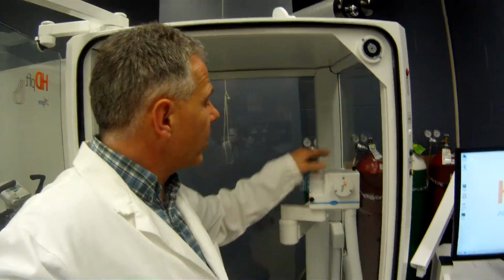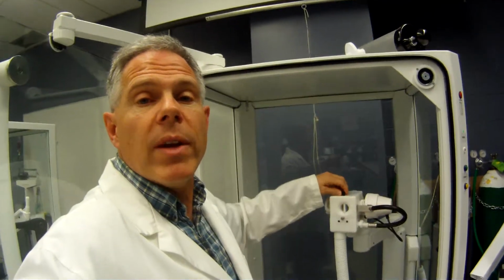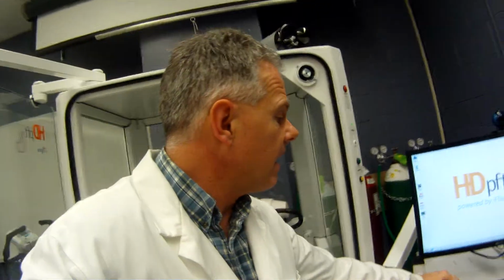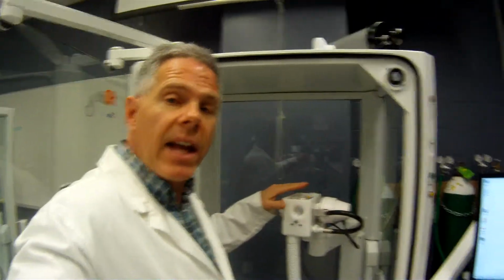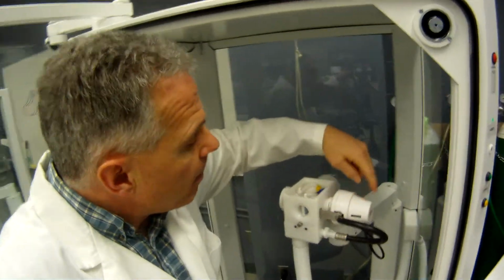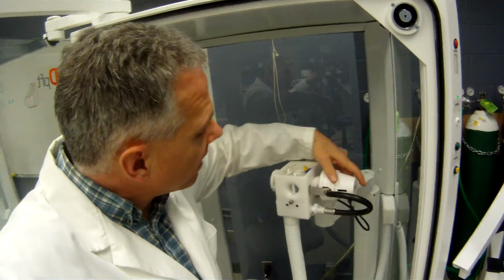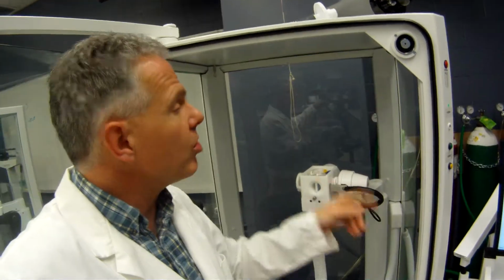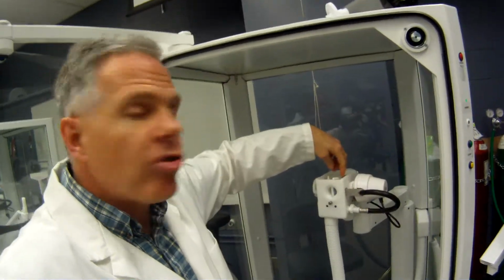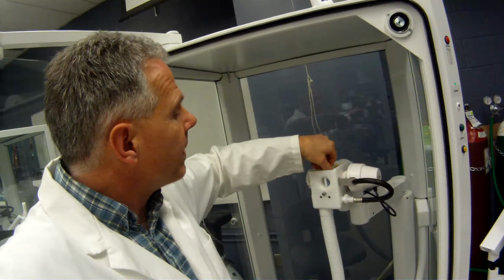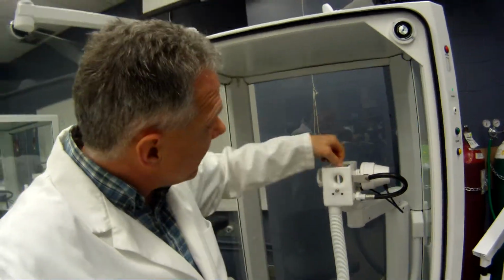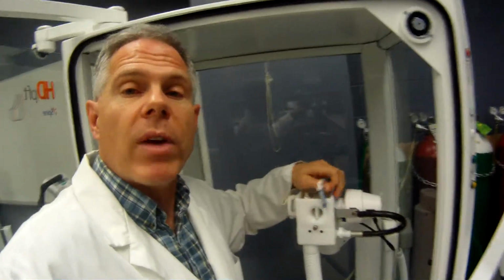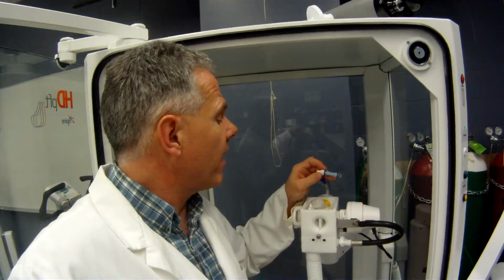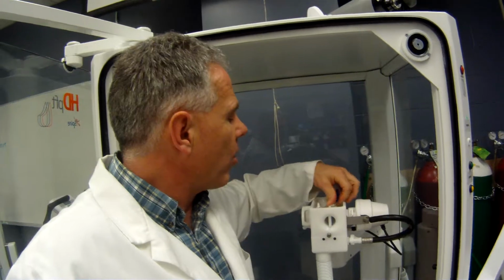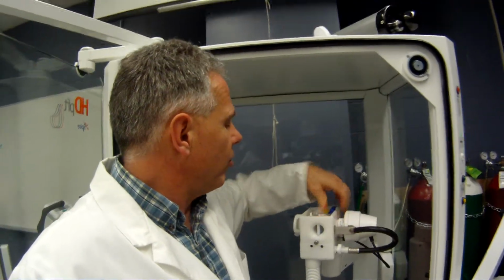Now this white part here you're looking at is also our gas control unit. So what this does is, if you're doing a specialty test, like a nitrogen washout or a DLCO, the patient will actually be breathing through here. This is our regulator. The gas flow, if it's 100% oxygen, or the DLCO mixture, comes up through here, and the patient will be breathing through this regulator right here. Now the way that gas flow is controlled is with a little kind of balloon valve right here. And these can rupture, so these need to be checked fairly often. So if you're trying to do a test and it's not working, it could be because that's ruptured. So we've got to check those every once in a while. So that's housed in this little unit here.